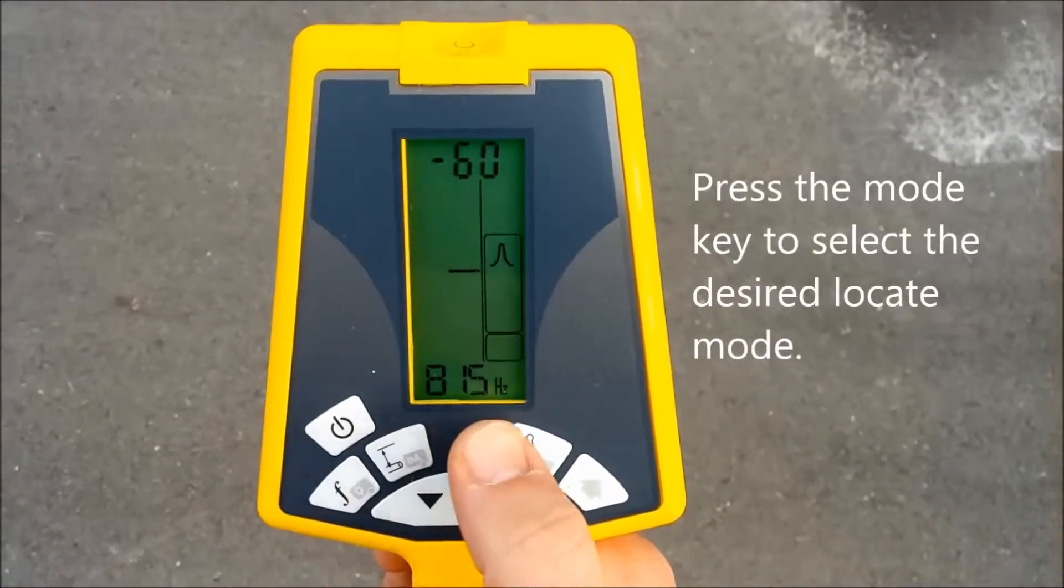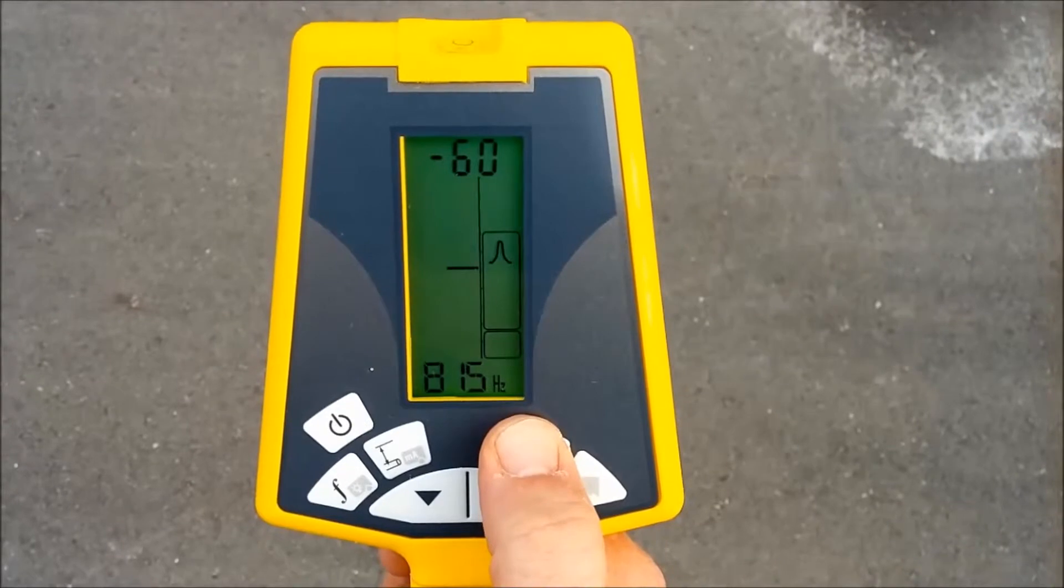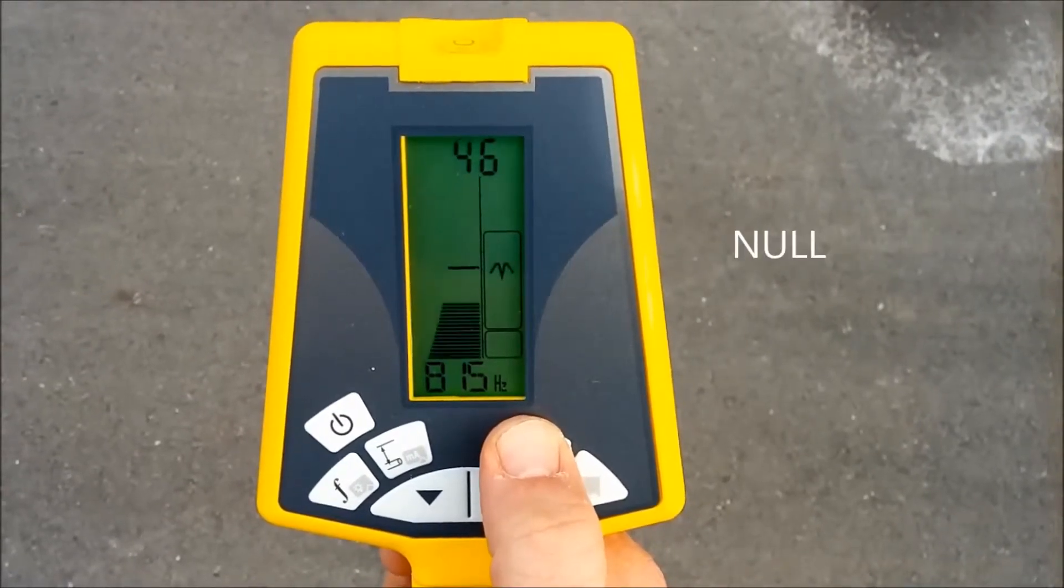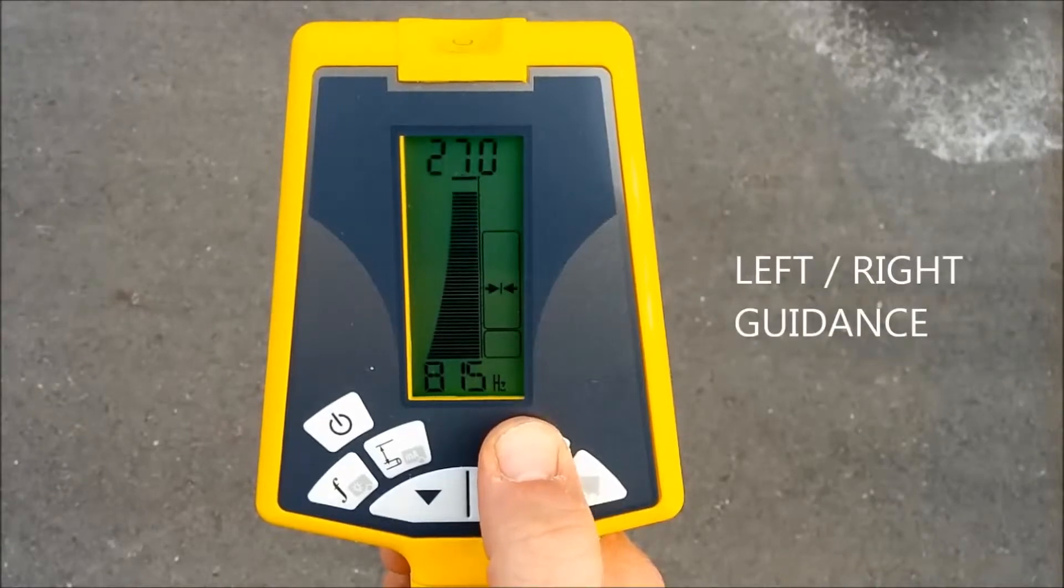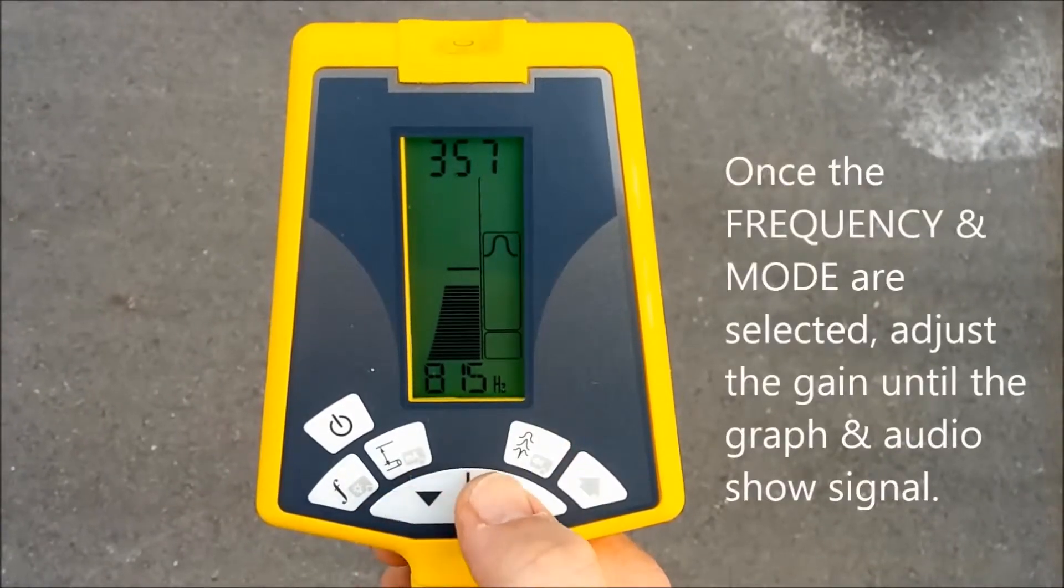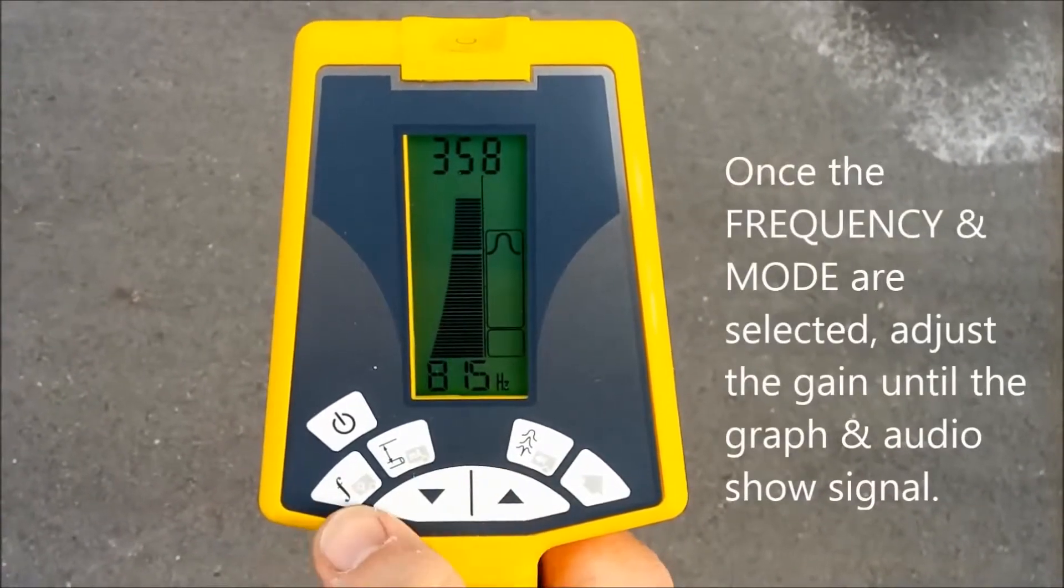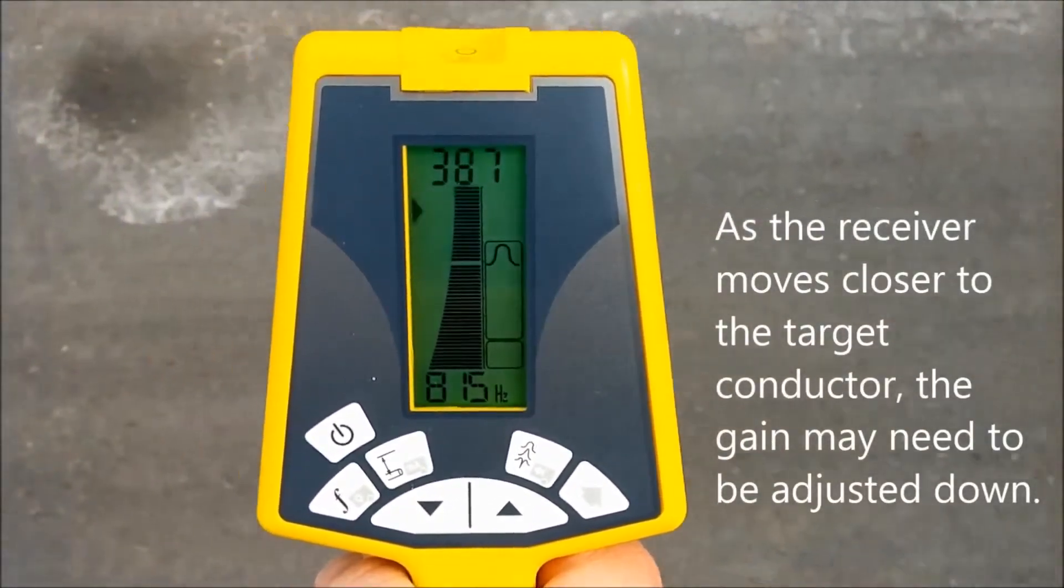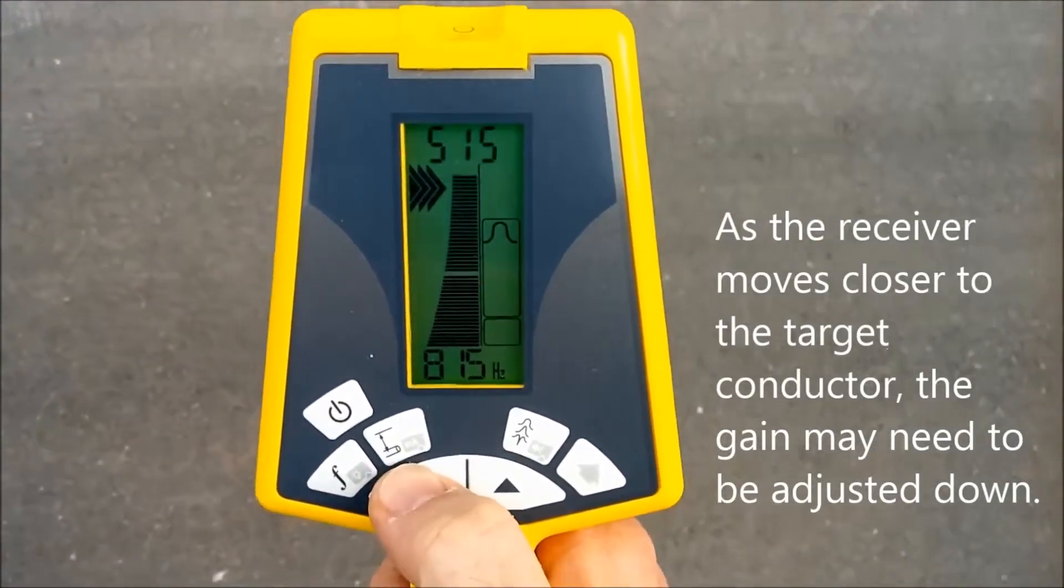Press the mode key to select the desired locate mode. Common modes include peak, pinpoint peak, null, and left-right guidance. Once the frequency and mode are selected, adjust the gain until the graph and audio show signal. As the receiver moves closer to the target conductor, the gain may need to be adjusted down.